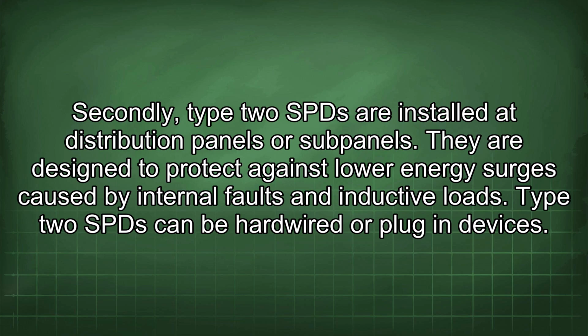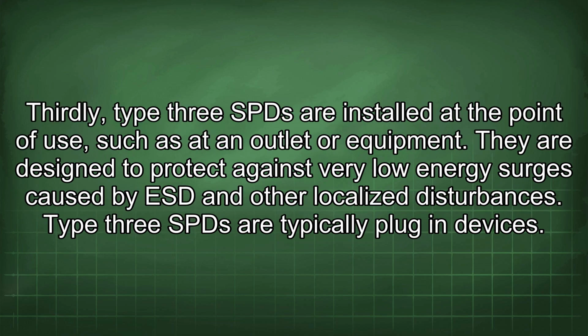Secondly, Type 2 SPDs are installed at distribution panels or subpanels. They are designed to protect against lower energy surges caused by internal faults and inductive loads. Type 2 SPDs can be hardwired or plug-in devices. Thirdly, Type 3 SPDs are installed at the point of use, such as at an outlet or equipment. They are designed to protect against very low energy surges caused by ESD and other localized disturbances. Type 3 SPDs are typically plug-in devices.